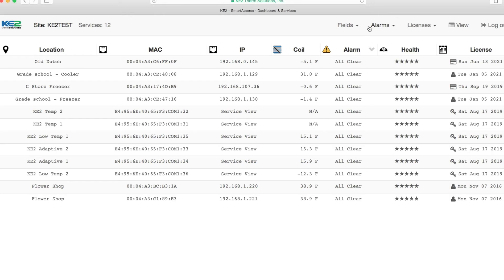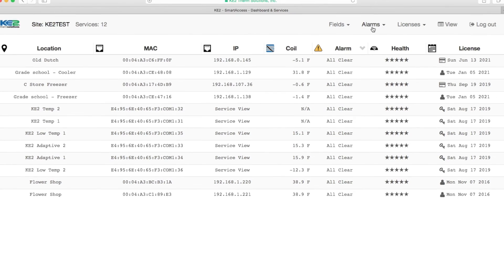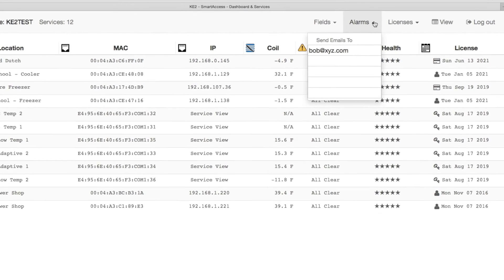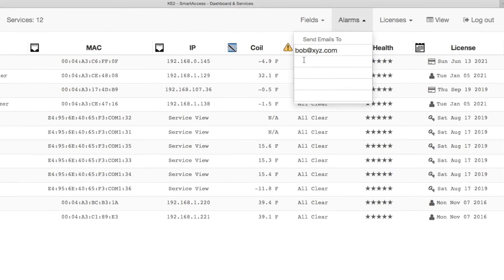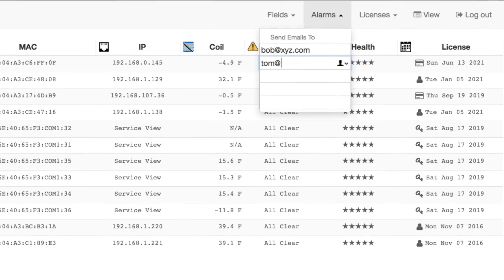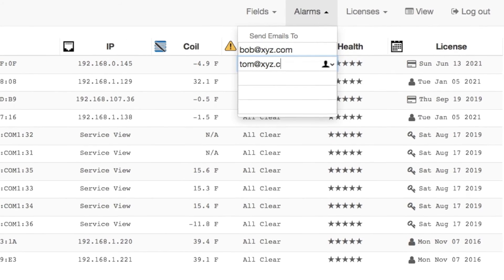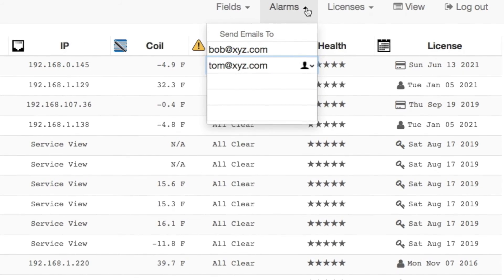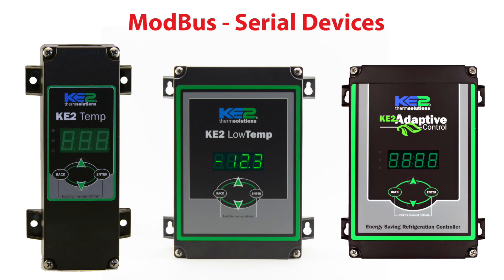Last but not least, one of the biggest advantages to KE2 Smart Access is the ability to have alarm alerts sent to multiple recipients via text or email. Let's set that up by clicking on the heading alarms. There are five spaces provided for email or text addresses. All of the controllers on the KE2 Smart Access site will alert you of an alarm condition regardless of whether they are Ethernet like the Key2Evap or serial Modbus like Key2Temps and Key2LowTemps.